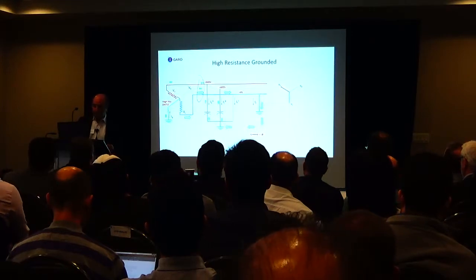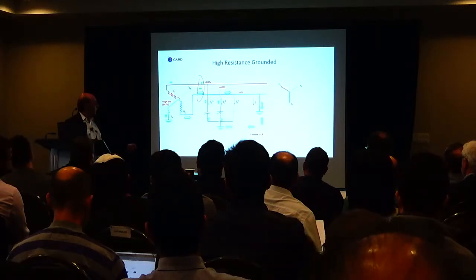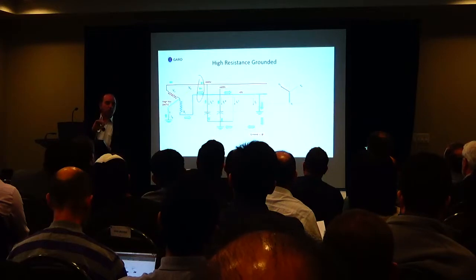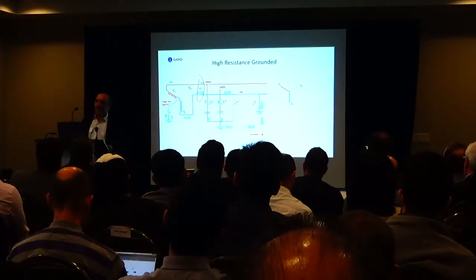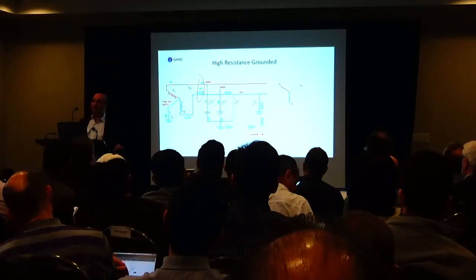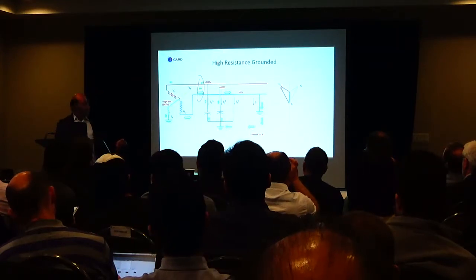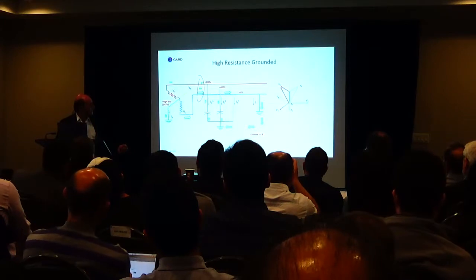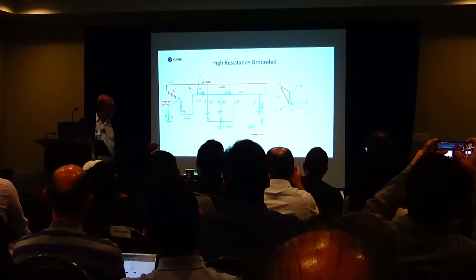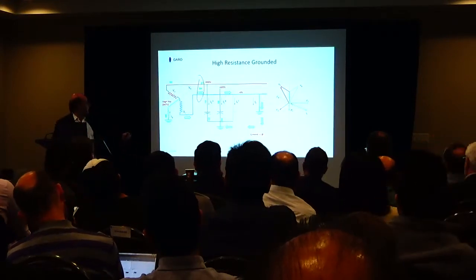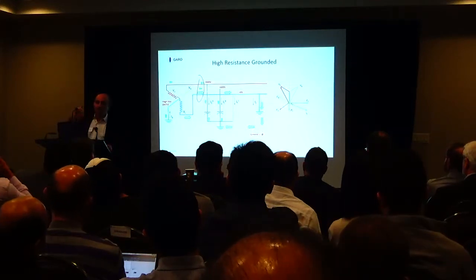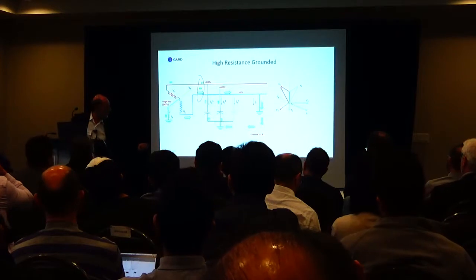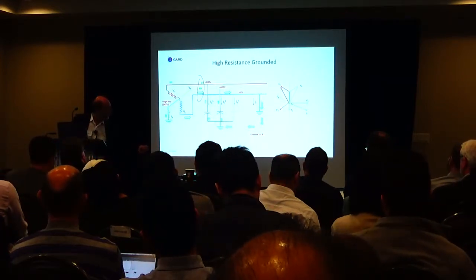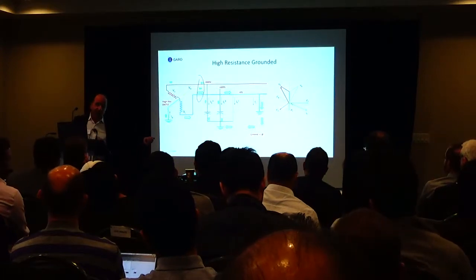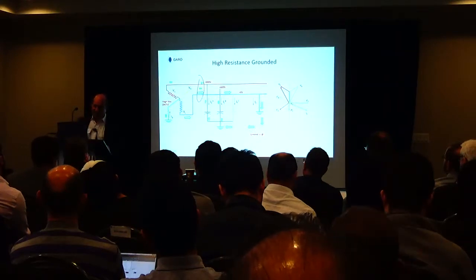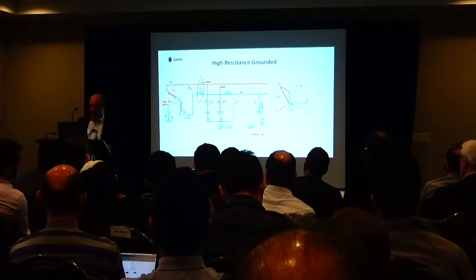Now we have a fault. So we're going to have a fault on C phase. The fault current returns back to the source. You have very, very low current flowing in an ungrounded system. The amount of current flowing in the ungrounded system is proportional to the capacitance and the distribution of your system. So it looks like this. The fault current is equal to the resistive current plus the capacitive current: the current going through here plus the current going through the capacitance. This is why Ajit said that the resistive current must be equal to or greater than the capacitive current. I haven't drawn it properly, my resistive current is smaller, but I did this for a different reason other than showing you which current is larger.